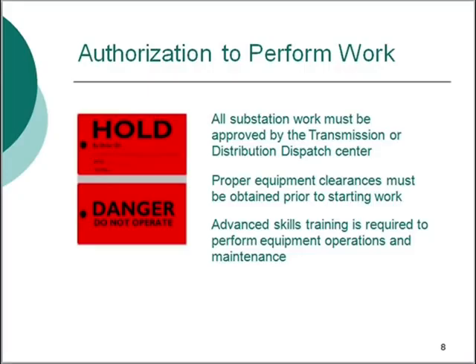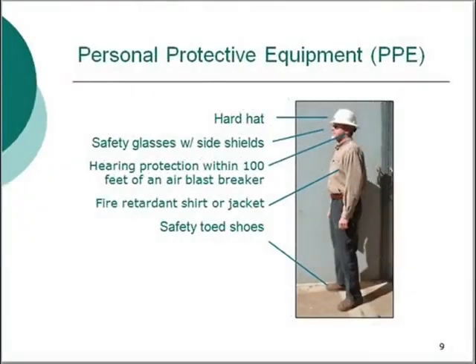Personnel are qualified only to the level of their training. This course is awareness level only, designed to identify the hazards in an electric substation. Completion of this course will enable you to enter a substation and perform tasks such as weed spraying, security checks, or visual checks like reading a gauge or meter. Advanced skills training is required to perform equipment operations and maintenance. The following personal protective equipment must be worn when working on or near energized equipment: hard hat, safety glasses with side shields, hearing protection within 100 feet of an air blast breaker, a fire retardant shirt or jacket, and safety-toed shoes. Any exemptions to this policy shall be determined through a hazard assessment and approved by the Safety and Health Manager.